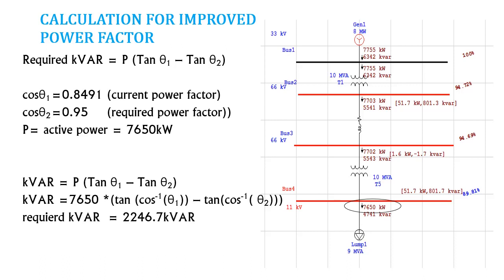So in order to find out the kVAR, I have written 7650 in place of P and for theta 1, I am actually taking the cos inverse of the power factor. And same for the theta 2 and when I am calculating this term, I will get 2246.7 kVAR. Now, let's apply this capacitor on SLD.